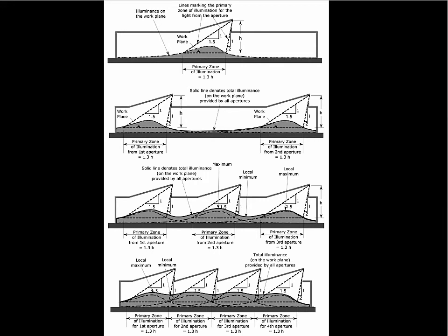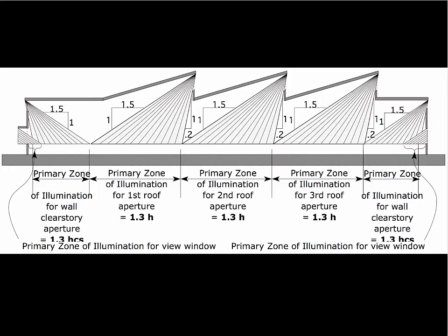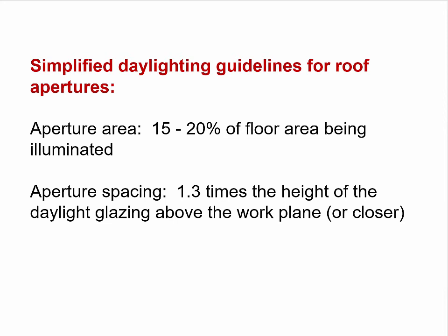We'll go through a series of examples examining the issue of aperture spacing, generating geometric constructs that help designers figure out appropriate spacing for roof apertures. We'll come up with simplified guidelines — for example, the area of glazing should be 15 to 20 percent of the floor area being illuminated, and the aperture spacing should be 1.3 times the height of the daylight glazing above the work plane. In a typical office or library, that work plane is taken as two and a half feet off the floor.